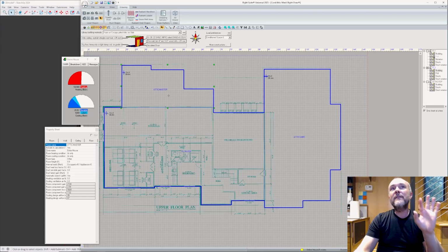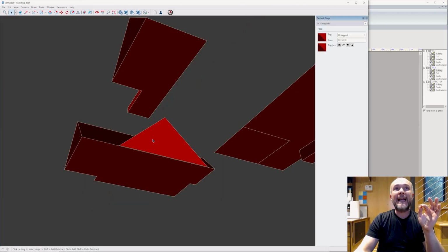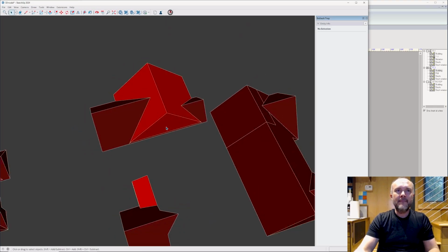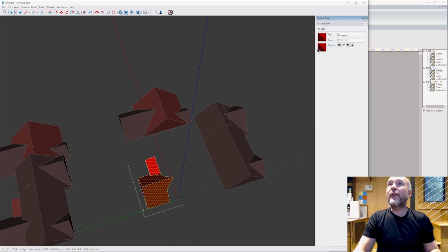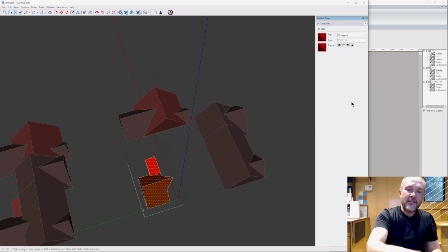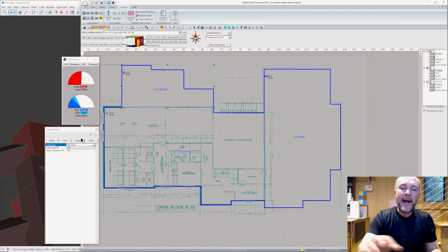Okay, so now we've got the volume in here correct. This is adding the right amount of volume. Now what we need to do is go into the surface area, because this attic is modeled right now to have 843 square feet of ceiling area. What it actually has is 1383. So we take 1383.15, I'm not going to bore you with decimal places, minus 843, and I've got a difference of 540.